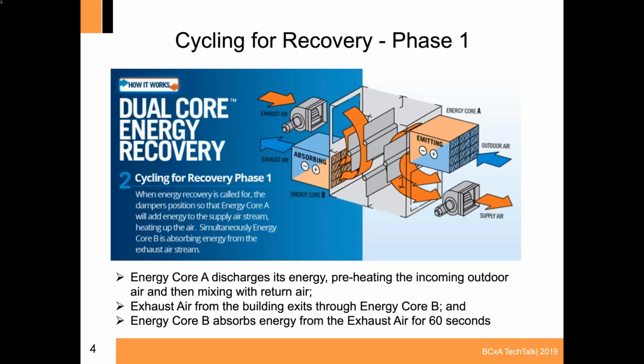For the cycling for energy recovery, this diagram assumes that the system has already been operating. You have the cold outdoor air coming into energy core A, which is the top right-hand corner of the diagram, and taking the energy out of the core, it's transferred into the airstream, which then mixes with some return air and is supplied to the building. On the other side, energy core B is in its charging cycle. The exhaust air or return air from the building is directed through the core and then exhausts out. This charges it, getting ready for when the cycle flips over.